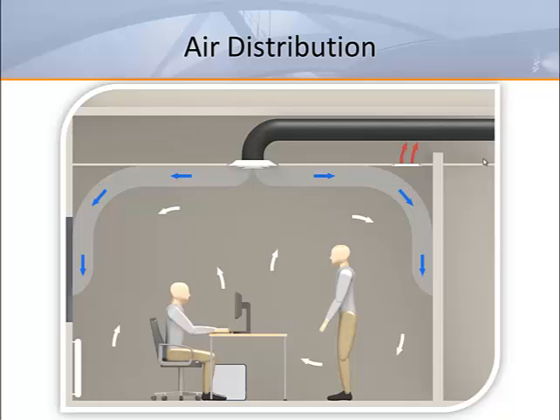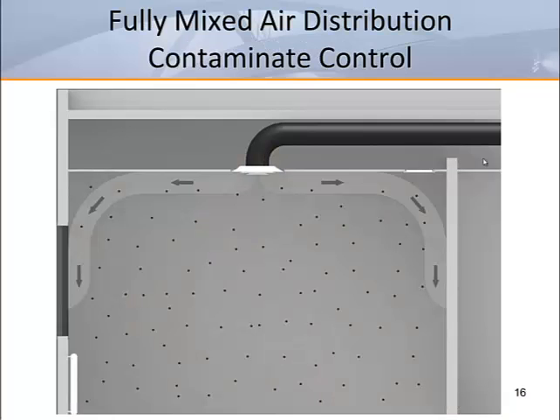With a fully mixed system, the first thing the supply air does is pick up heat from overhead lighting. This is the reason why we typically need a 20-degree differential temperature on the supply air. A disadvantage of fully mixed systems is that lightweight contaminants will continue to swirl around in the occupied space. A good example for schools is the contamination from an uncovered sneeze being carried from one occupant to another.